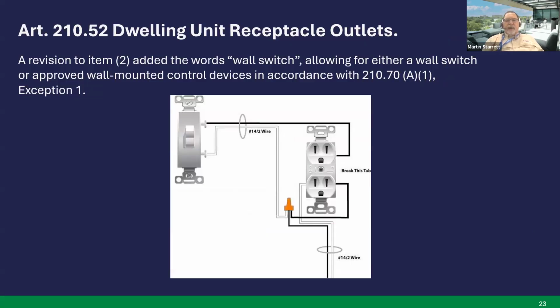Article 210.52, dwelling unit receptacle outlets. A revision to item 2 added the words "wall switch," allowing for either a wall switch or approved wall-mounted control device in accordance with 210.70(A)(1), exception 1. Previously, in 2023, it only had approved wall-mounted control devices. So basically, they added the words wall switch to line up with 210.70(A)(1), exception 1. You'll find a lot of changes in the 2026 are just little things that make sense, or if one article says it, then this other article should say it as well. So that's what they did here by adding the words wall switch. Next slide.